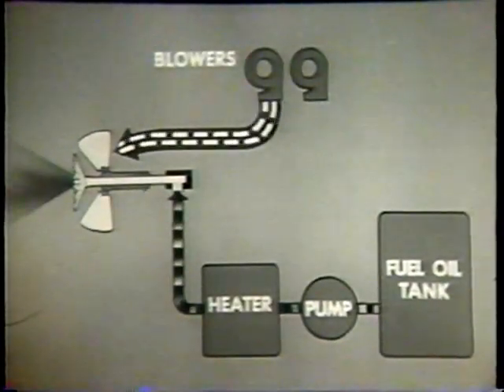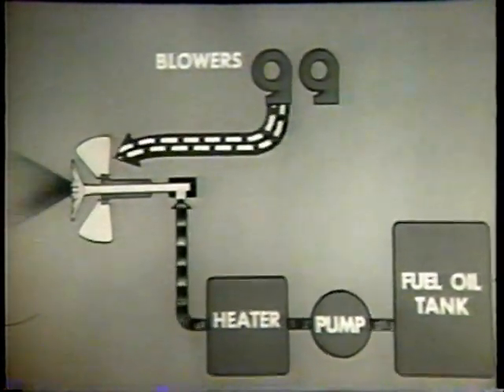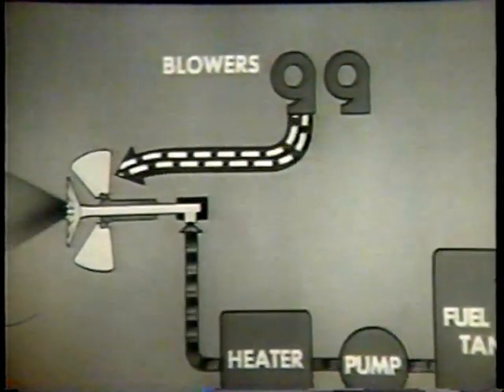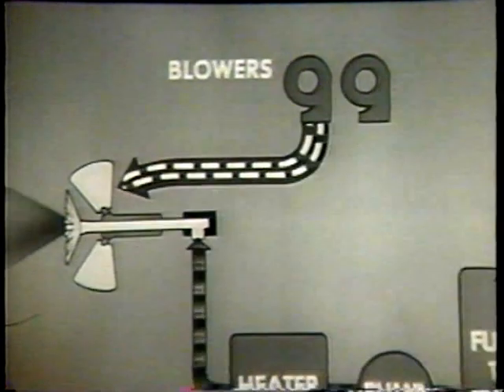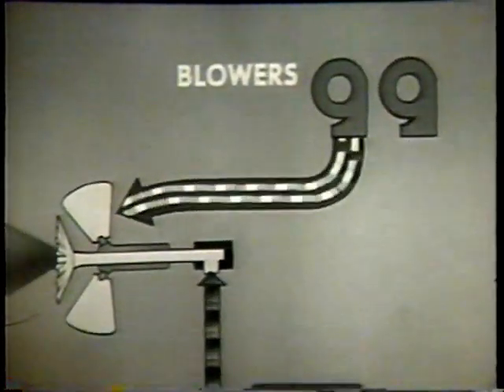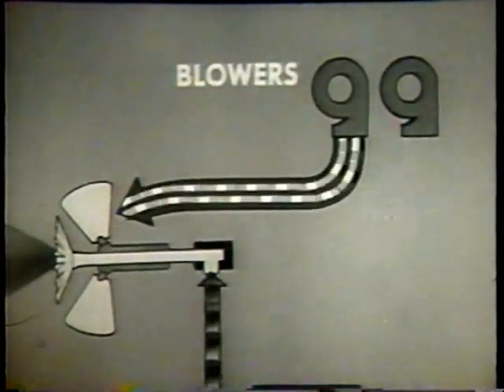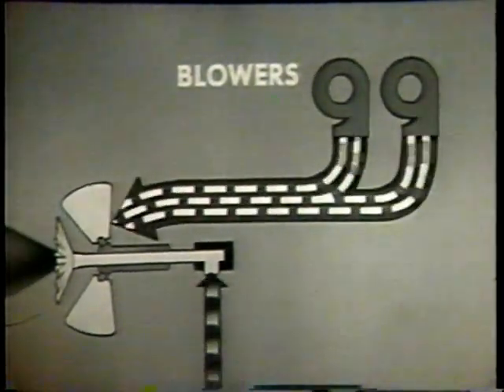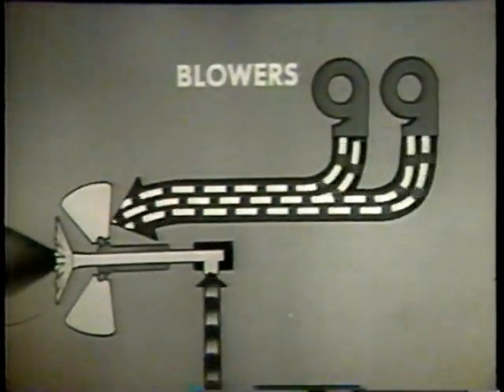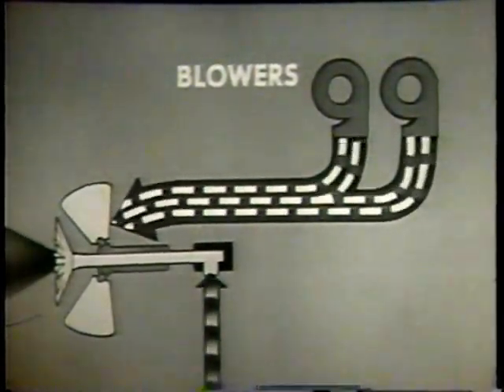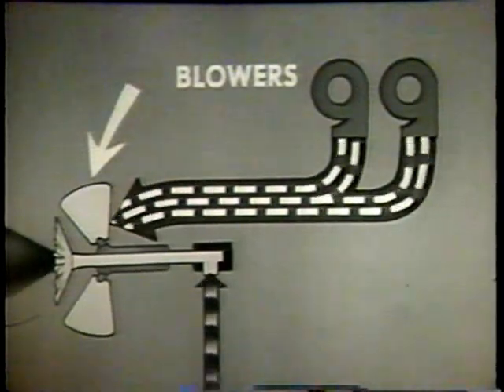Controlling the force draft blowers is the principal method of controlling the quantity of air reaching the burner. For example, to increase the air a moderate amount, you increase the speed of the blower in service. Or, if even more air is needed, you cut in another blower. You can make minor adjustments in the air supply with the air doors.